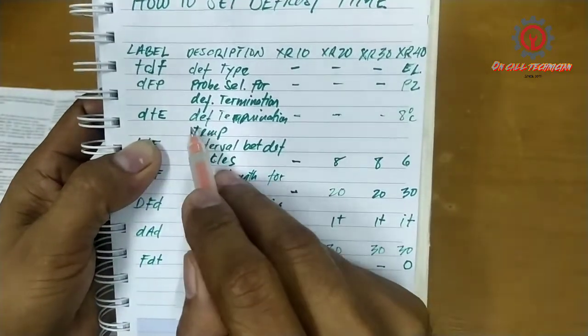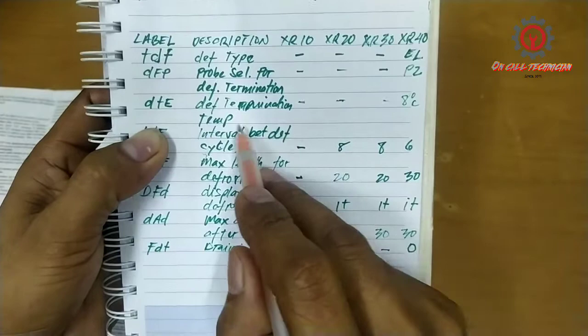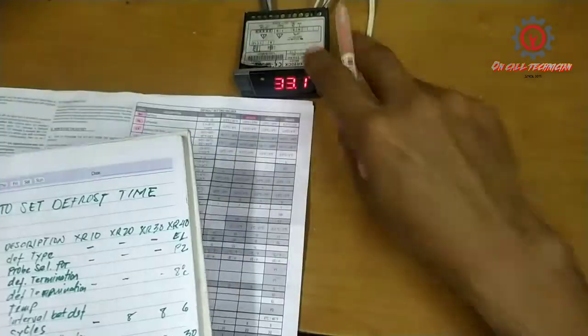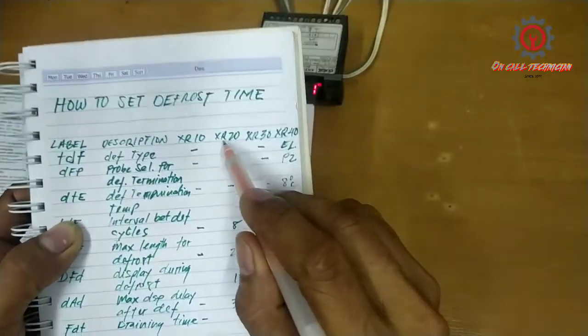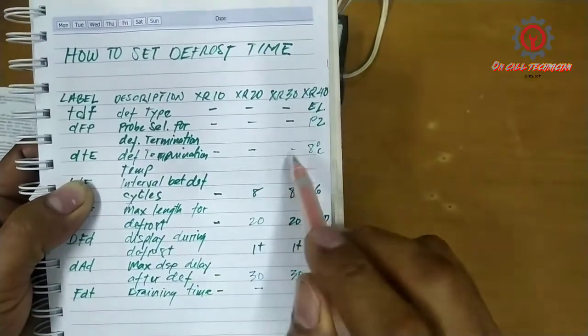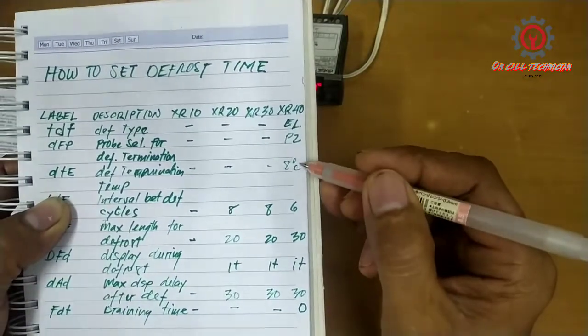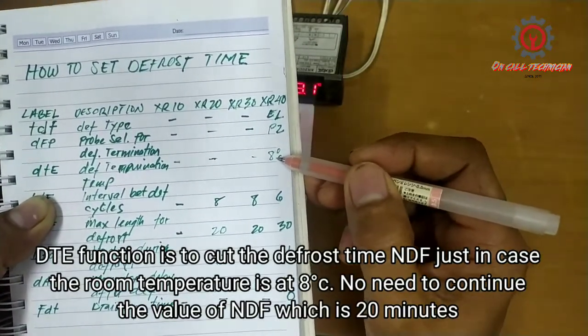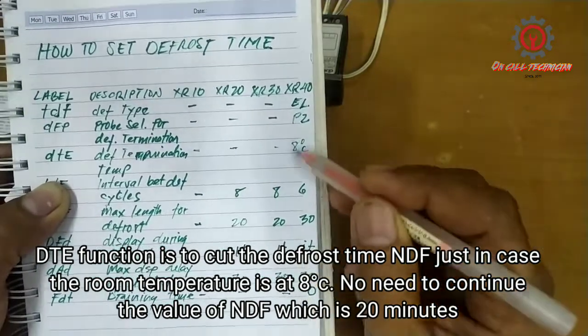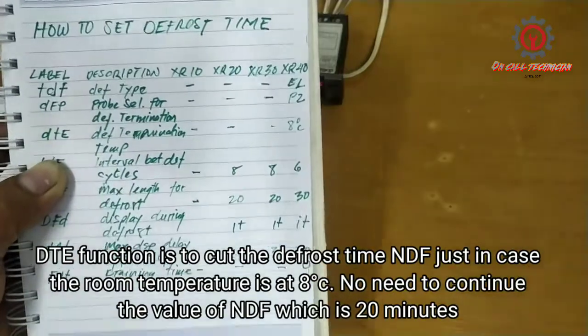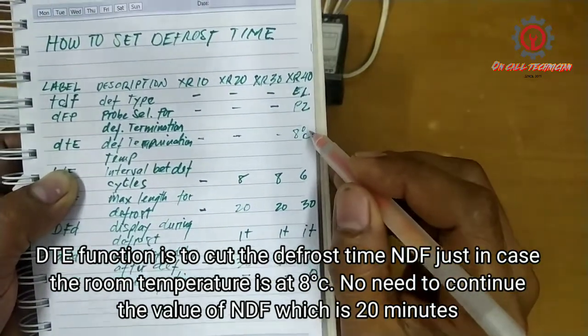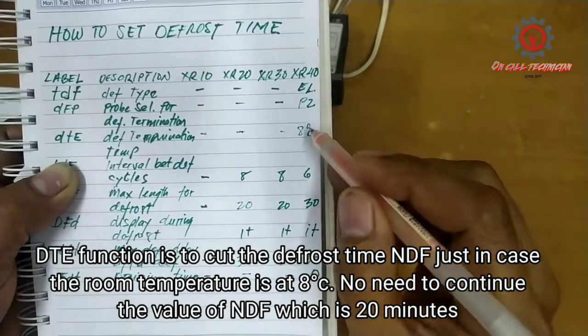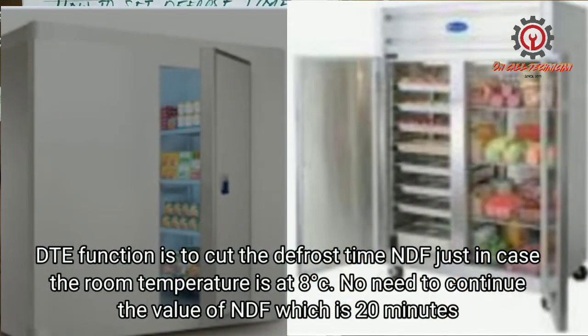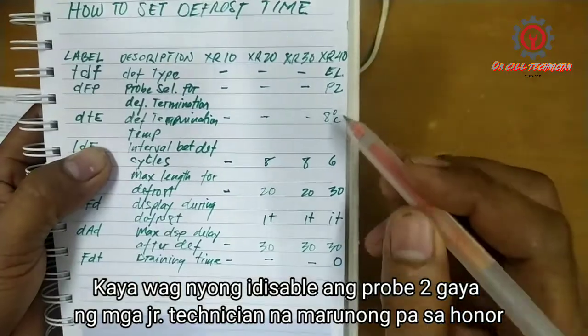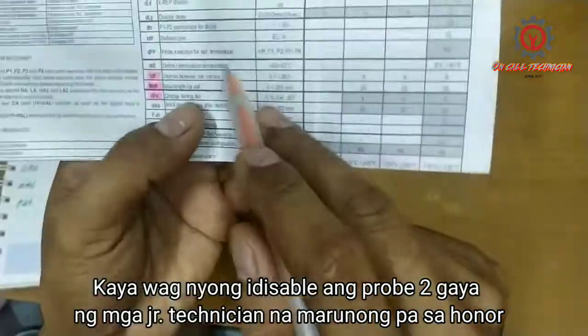And next guys is the DTE. And the DTE guys is the defrost termination temperature. In this Dixell, it doesn't have, because XR20 doesn't have, together with 10 and 30. But in the model 40, it has. So they put a value of 8 degrees Celsius, which is good for both chiller and freezer. Tamang-tama lang tong 8 degrees Celsius guys, para sa chiller at para sa freezer na ating commercial refrigerator. That's why I'm not recommending to disable the P2 sensor for the IDF.